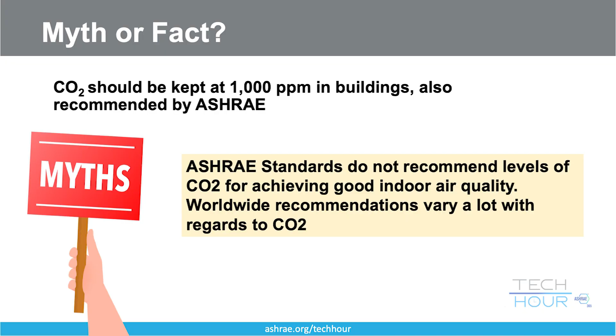Now, moving on to a topic that we hear a lot about: carbon dioxide. The question for you here is, is this a myth or fact? Carbon dioxide should be kept at 1,000 ppm in buildings, also recommended by ASHRAE. That's actually a myth. In reality, ASHRAE sets no CO2 limit for achieving acceptable indoor air quality. This number, 1,000 ppm, is a legacy misconception and was never a health threshold.